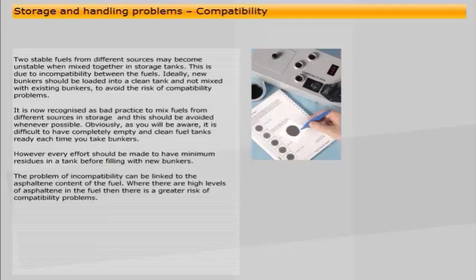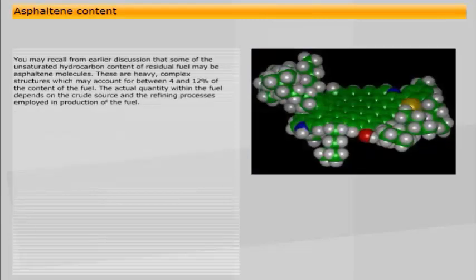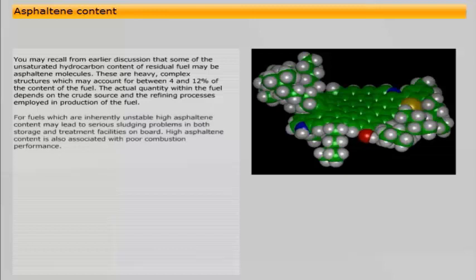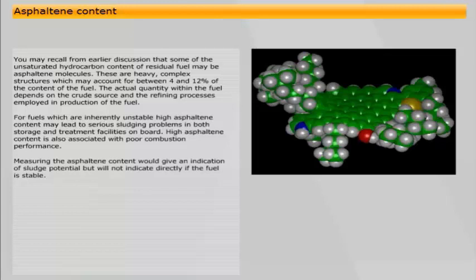The problem of incompatibility can be linked to the asphaltene content of the fuel. Where there are high levels of asphaltene in the fuel, then there is a greater risk of compatibility problems. You may recall from earlier discussion that some of the unsaturated hydrocarbon content of residual fuel may be asphaltene molecules. These are heavy, complex structures which may account for between 4 and 12% of the content of the fuel. The actual quantity within the fuel depends on the crude source and the refining processes employed in production of the fuel. For fuels which are inherently unstable, high asphaltene content may lead to serious sludging problems in both storage and treatment facilities on board. High asphaltene content is also associated with poor combustion performance. Measuring the asphaltene content would give an indication of sludge potential, but will not indicate directly if the fuel is stable.